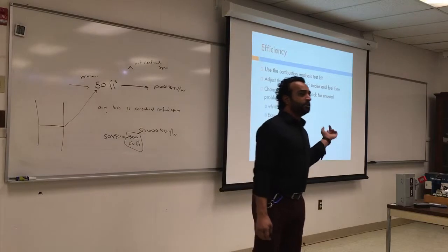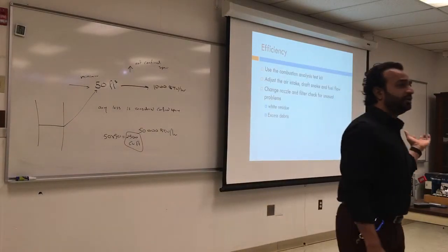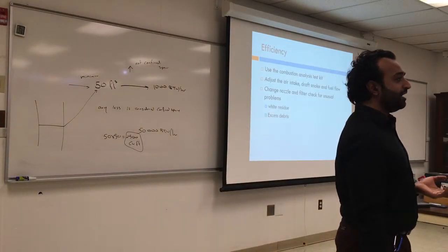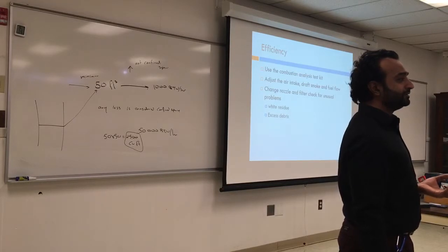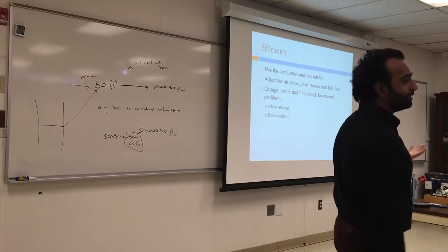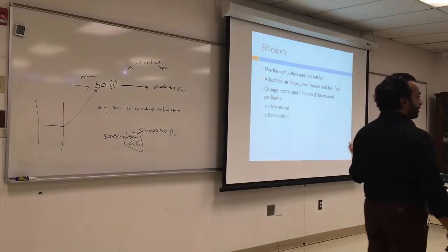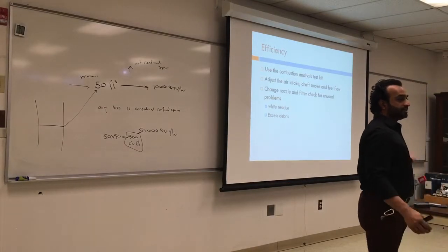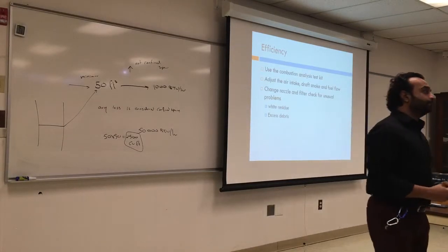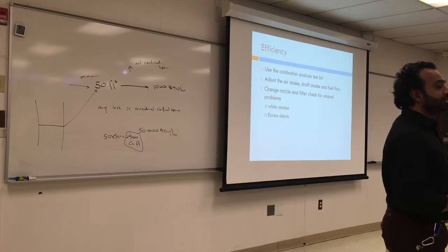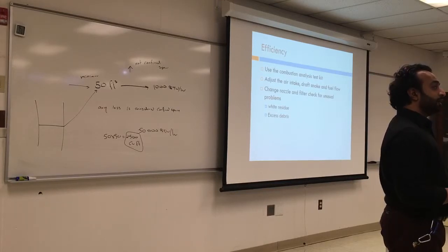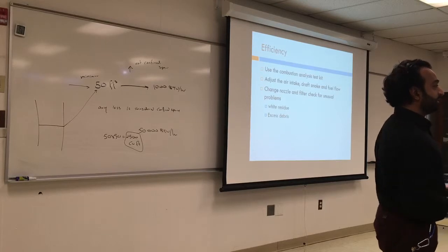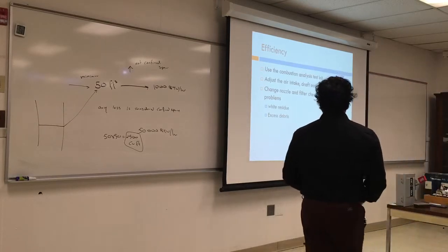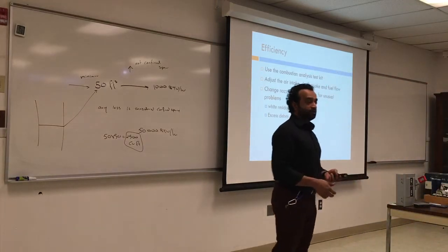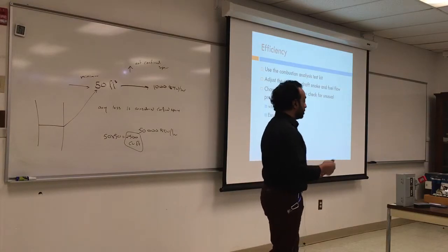The white residue is usually caused because of bacteria. If you have bacteria, that means you have what? Water. Thank you. There's water in the tank. Go check the water, drain the water, make sure it's clean and inspected. These things, even though everybody says it should be done annually, not everybody does it. People don't check for water. They will just fill the tank and move on. Be the one who actually checks for those issues because over time they will cause a problem.